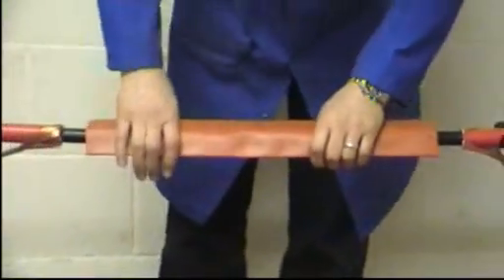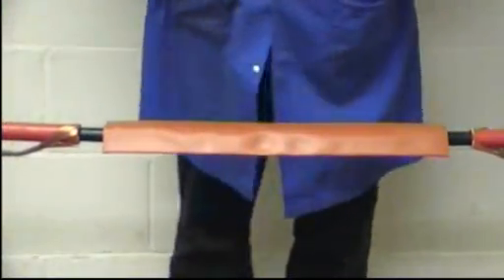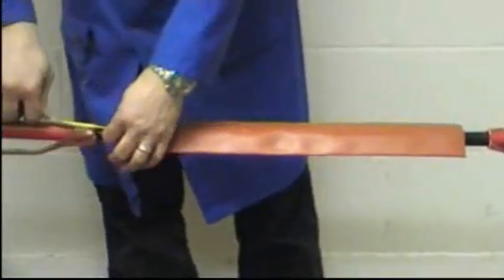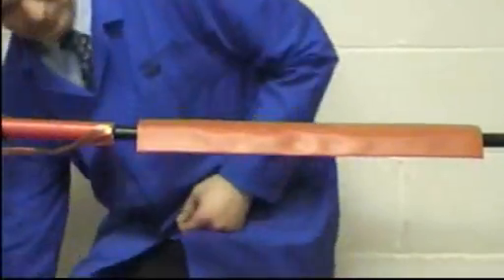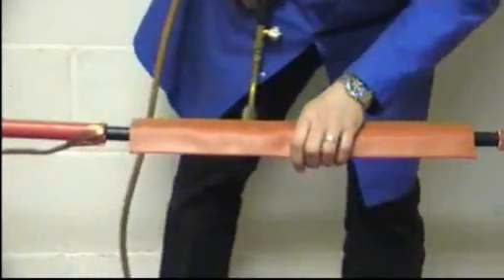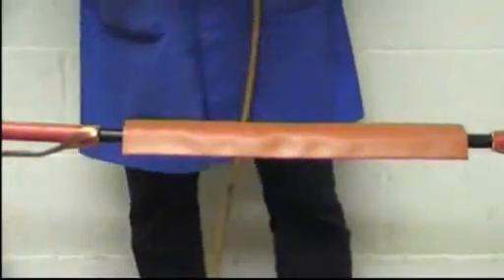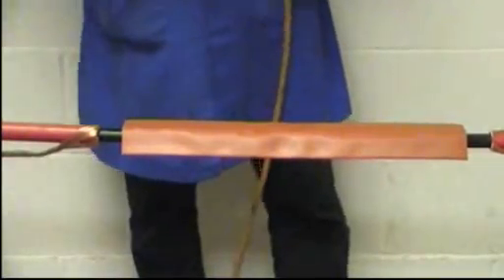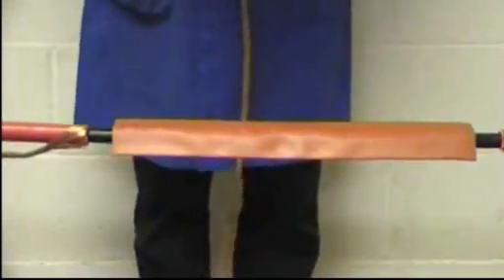Now as this is a 33 kV joint, additional layers of insulation are added. Centre up the tube directly over the stress control tube. And once again, start shrinking from the centre to one end at a time.